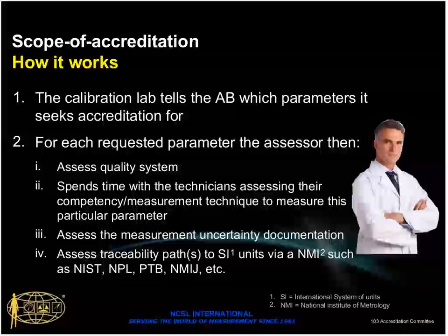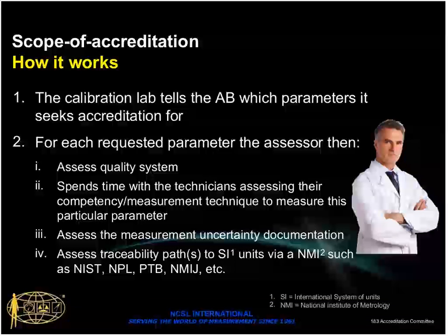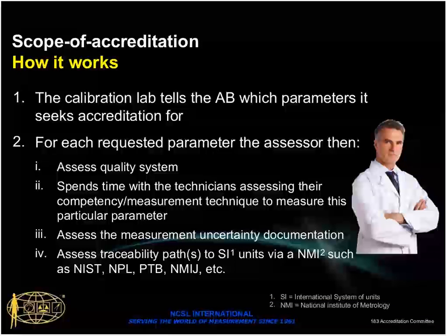And again, if you're using non-accredited services, most companies who are accredited would have the same traceability arrangements with varying uncertainties, even for non-accredited work. In the United States, the traceability is usually to NIST.